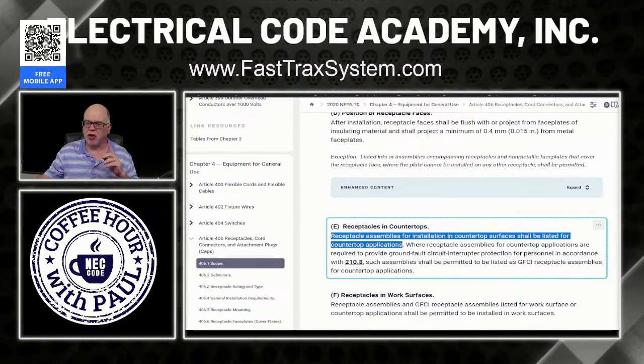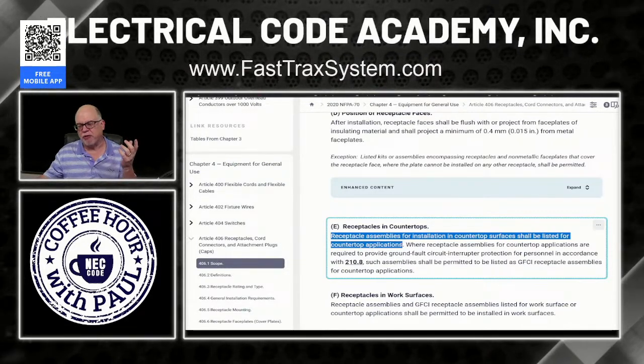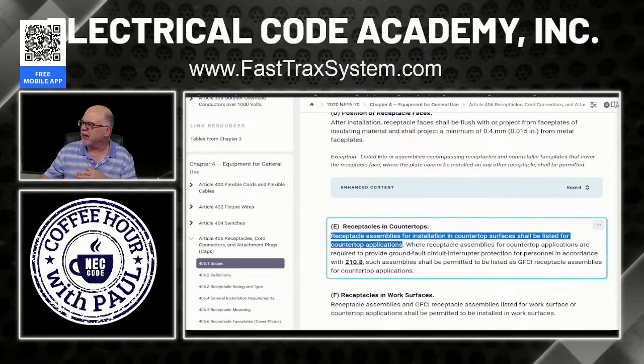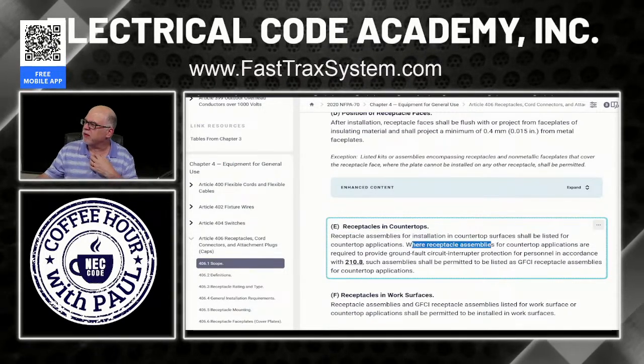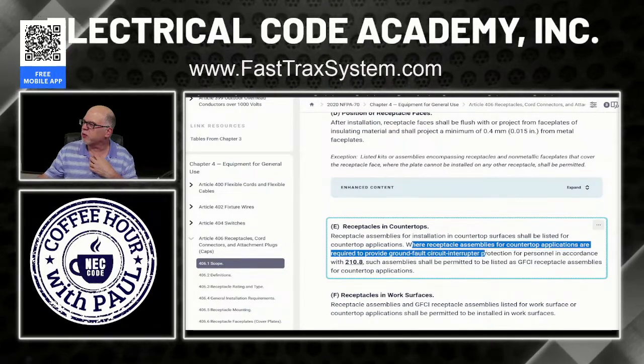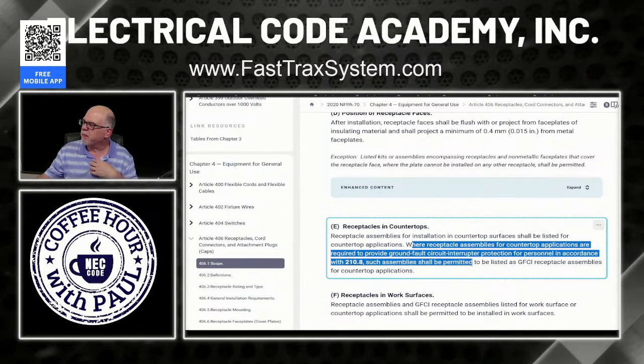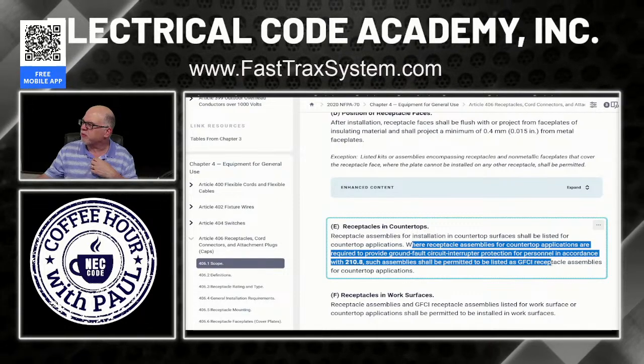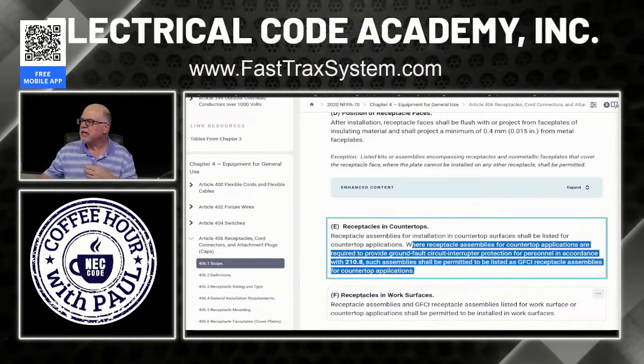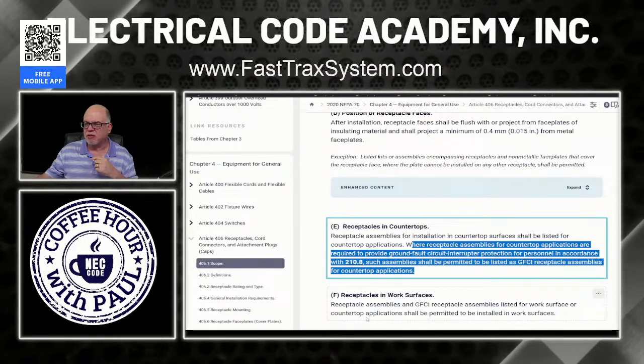Remember what I said earlier, that I can't use those pop-ups that have a cord and plug on it. That's more like a relocatable power tap. They have to be hardwired, and they're going to be listed for this. Now, it says where the receptacle assemblies for countertop applications are required to provide ground fault circuit interrupter protection for personnel in accordance with 210.8, such assemblies shall be permitted to be listed as GFCI receptacle assemblies for countertop applications. So, can I have them in it? Absolutely. But what about that face-up application?